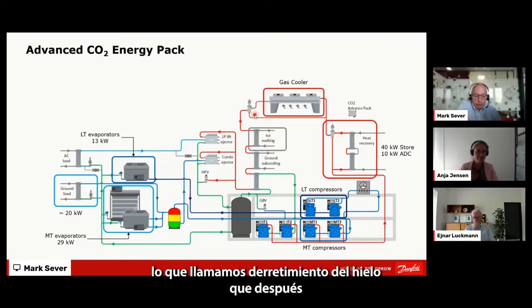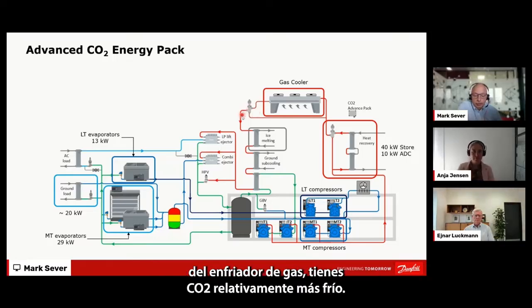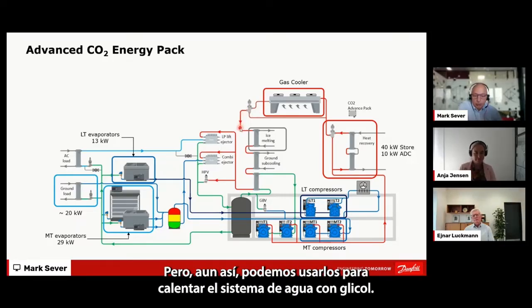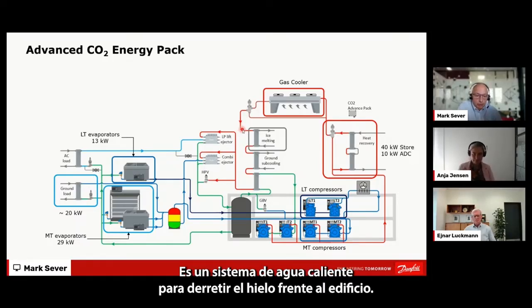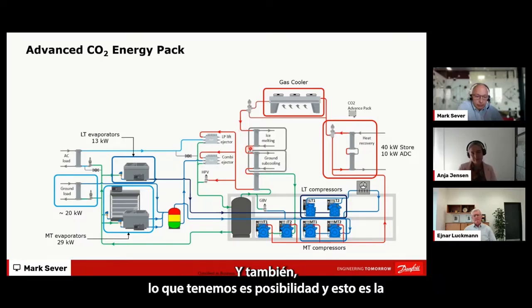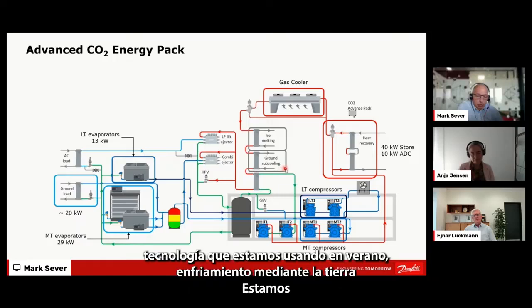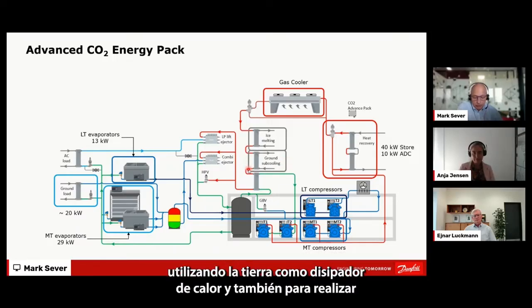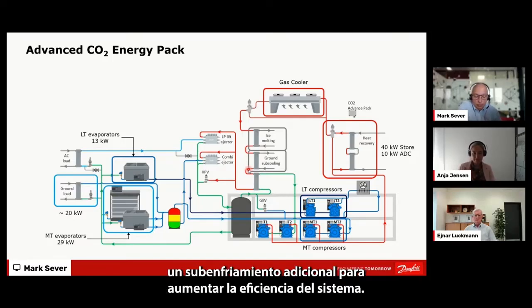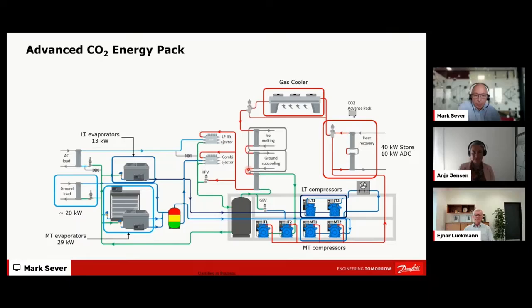But what is additional also? We also have a technology that we call ice melting. After the gas cooler, you have a relatively colder CO2, but we can still use it to heat up the glycol water system, a hot water system, to melt ice in front of the building. We also have a possibility, a technology we use in the summertime: ground cooling, where we use the ground as a heat sink to do additional subcooling and increase the efficiency of the system even more.